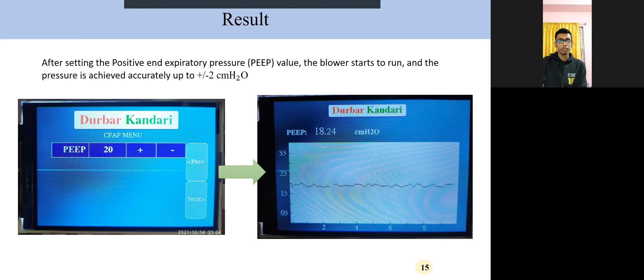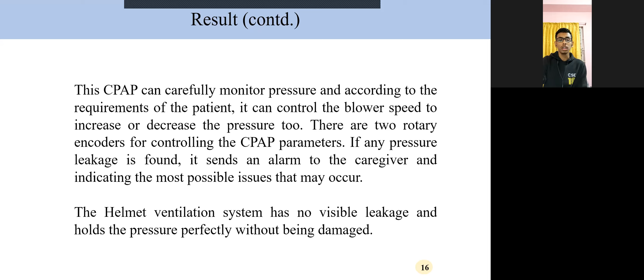This CPAP can carefully monitor pressure according to the requirement of the patient. It can control the blower speed to increase or decrease the pressure flow. There are two rotary encoders for controlling the CPAP parameters. The user interface is very easy to learn and control. If any pressure leakage is found, it sends an alarm to the caregiver using the buzzer. And also it indicates the most possible issues that may occur. The helmet ventilation system has no visible leakage and holds the pressure perfectly without being damaged.